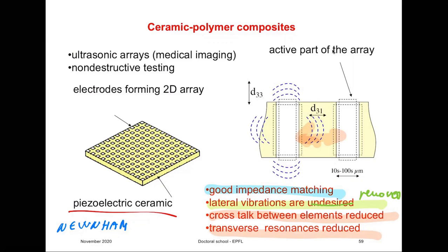You see that the ceramic piece is completely available to the acoustic wave, both for emission and reception. So the polymer doesn't interfere with the piezoelectric effect, but you reduce capacitance, you reduce density, and you reduce the crosstalk. You can also use this as an array because each of these elements is independent in the composite, thanks to the polymer.